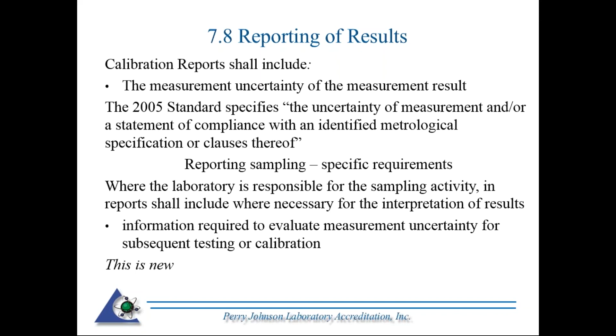Okay, decision rule again, that we specified during contract review. If a customer is specifying a statement of compliance with a metrological specification, i.e. pass, fail, in tolerance, out of tolerance, the decision rule has to be discussed, documented up front, and it has to be documented on the report. So basically, this is specifying that you have to identify the decision rule on the report.